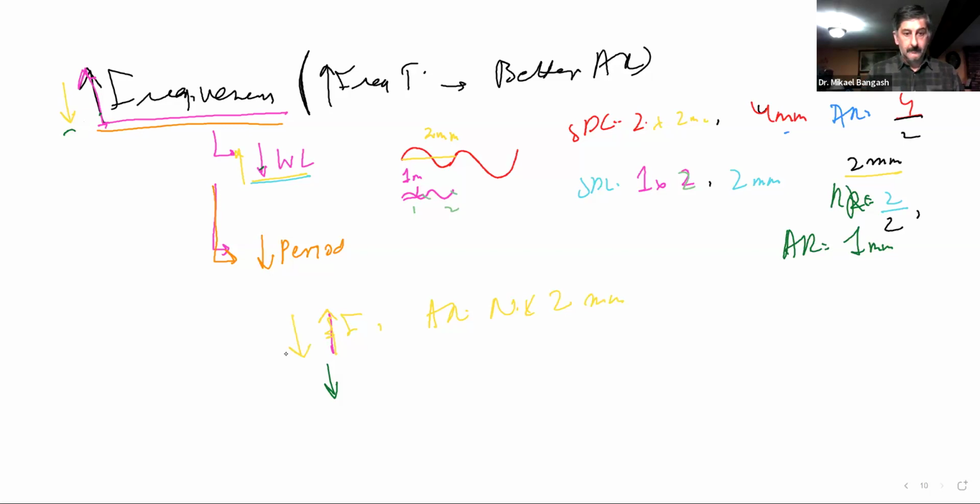The low frequency has a greater numerical value, whereas the high frequency has a lower numerical value. Which means that in this case, the distance has to be at least 2 millimeters for these two structures, shallow and deep, to be distinctly displayed.